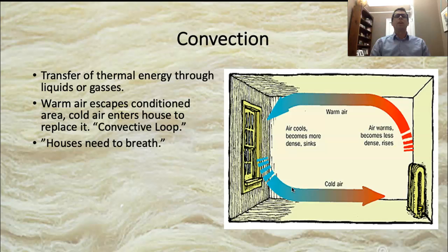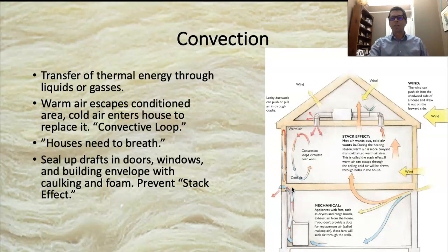The other thing that can happen here is if you're actually losing air, and where that usually happens is you're losing it up into the attic because lights aren't sealed, plumbing fixtures aren't sealed. Air is going to escape into those unconditioned areas, and air is going to be replaced somehow, okay? It's going to maintain a constant pressure. So if you let air escape into the attic, it's going to pull it in from anywhere else it can, okay? And this is called the stack effect.